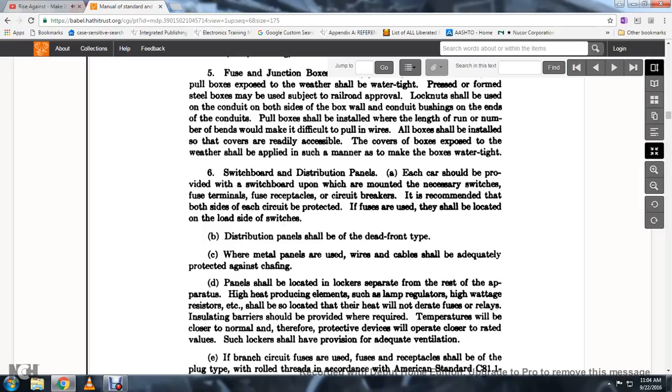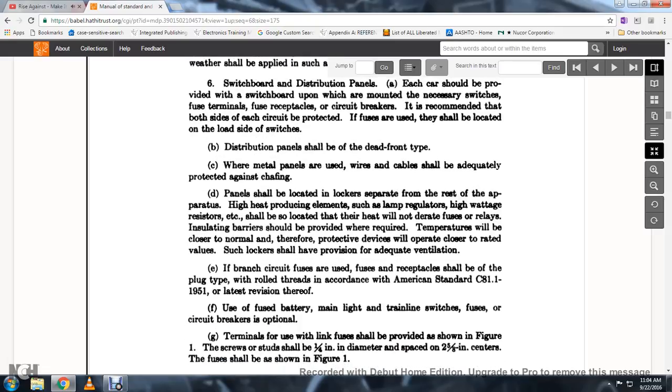Panels should be located in separate lockers from the rest of the apparatus. The heating producing elements, lamp regulators, high wattage resistors, etc., shall be located where the heat will not deteriorate the fuse or relays. Insulating barriers should be provided where required so temperature will be closer to normal, thereby protecting devices to operate closer to rated values. Such lockers shall have provision for adequate ventilation.